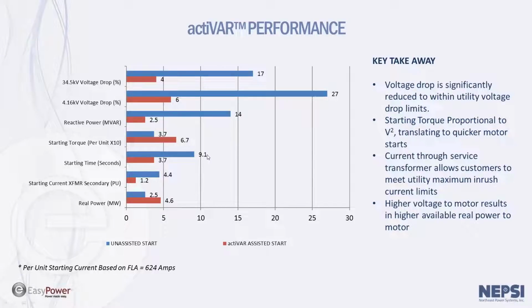It went from 9.1 seconds down to 3.7 seconds. So overall, the actiVAR or the capacitor assist start can provide near full torque to the motor and can virtually eliminate the voltage sag. In fact, we could increase the capacitor bank ratings here to a point where there'd be no voltage sag during starting. But since the limits are set at 4% for this utility, we size the actiVAR to limit that voltage drop to just 4%. And that saves in the cost of the actiVAR because it's a smaller piece of equipment.